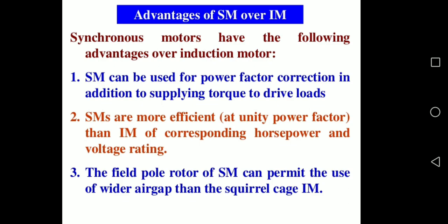Advantages of a synchronous machine over an induction machine. Synchronous motors have the following advantages over an induction motor. Synchronous machines can be used for power factor correction in addition to supplying torque to drive loads. They can be used for power factor correction because synchronous machines can act at lagging, leading and unity power factor conditions.